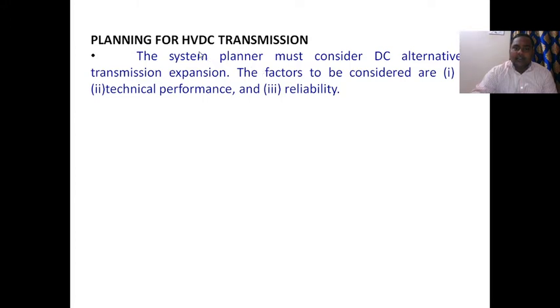While designing or erecting the HVDC transmission, you must keep in mind the cost point of view, technical performance, that is skin effects and corona loss, and third, reliability. From the reliability point of view, HVDC is better. In technical performance, HVDC is better. In initial cost, HVAC is better. Initially means capital cost. The capital cost of AC is very low because there are no converter stations. Whenever there are no converter stations, the filter equipment required is also less.